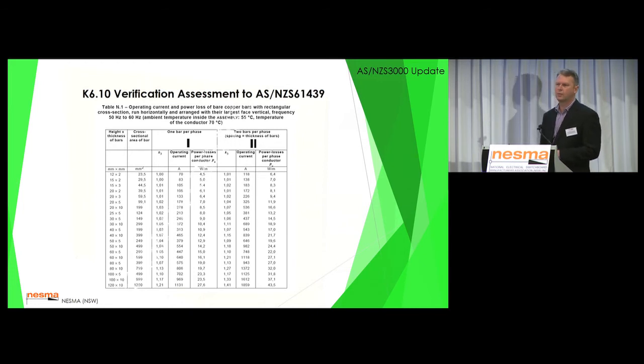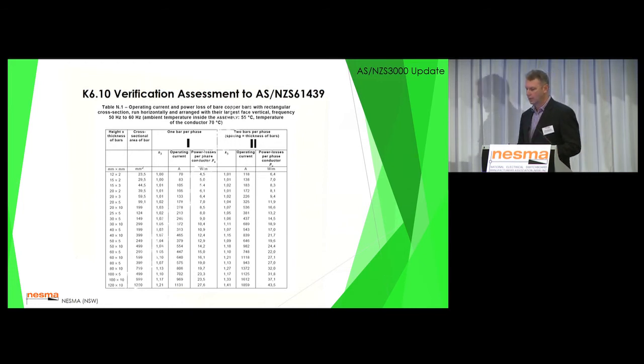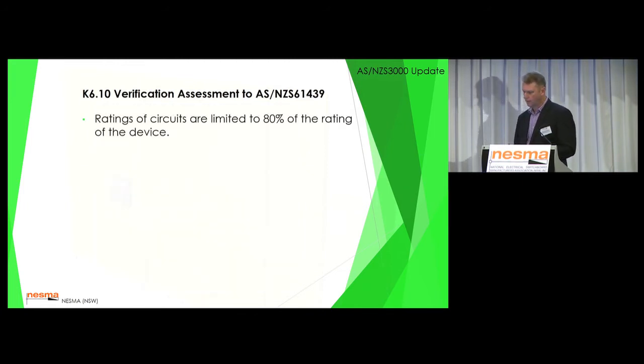We don't have table N1 in AS3000 still, but this is quite a conservative rating of copper bus bars inside an enclosure. Further to this, if you've done verification, you may end up with better results out of calculation. You may end up with better results again out of test. So verification assessment is when we're using calculations to come up with our temperature rise in this situation.